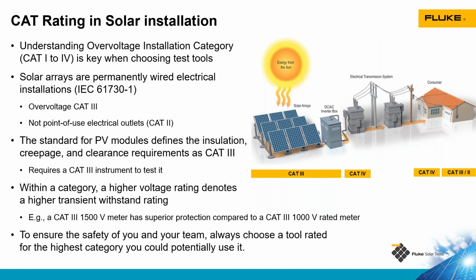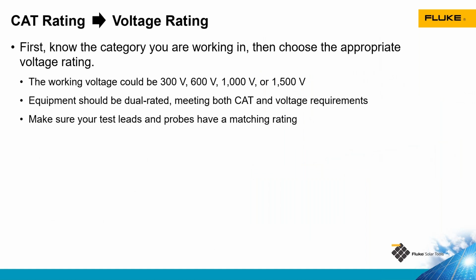Within a same category rating, as the voltage level of the tool goes up, the ability to withstand those transient voltage spikes increases as well. Once we know the category that we're working in, that's our environment, Category 3 on the array side, often Category 4 on the AC output side of the inverter, we need to know what voltage we're going to be operating at, or we're doing our testing at.